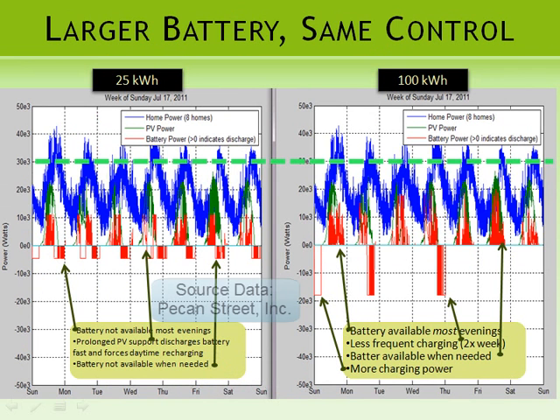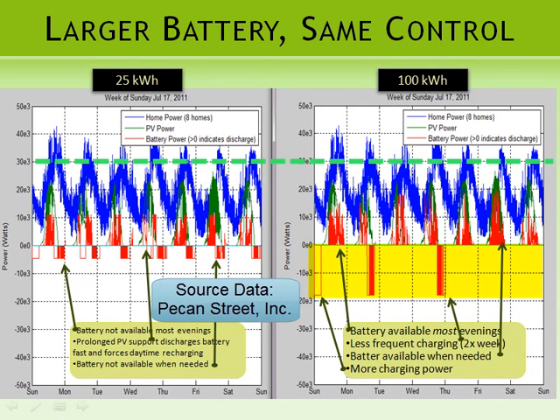What happens if we keep the same control strategy but increase the battery size to 100 kWh? While this may not be economically or physically viable, the results are still of interest to the manufacturers. Comparing the red curves, the larger battery is available in the evenings while the smaller one is not. Also, the larger battery undergoes fewer charging cycles per week. At the same time, the charging power of the larger battery is significantly higher, which can increase the transformer demand. While this appears to be a good solution, it does not address the control strategy. In this type of small-scale storage, it is preferable to revisit the control strategy rather than to construct a larger battery.